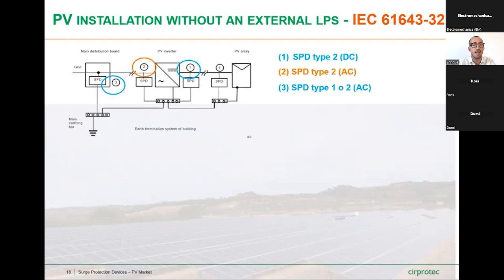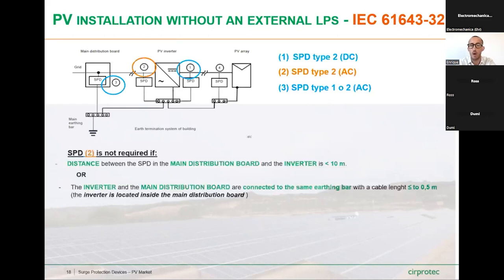Then there is an additional SPD that could be placed in the location 2. This one will not be required if the distance between the SPD in the main distribution board, the one located in the location 3, and the inverter is below 10 meters. Or if the inverter and the main distribution board are connected to the same earthing bar with a cable length equal or below to 0.5 meters. For example, a case is when the inverter is located inside the main distribution board.